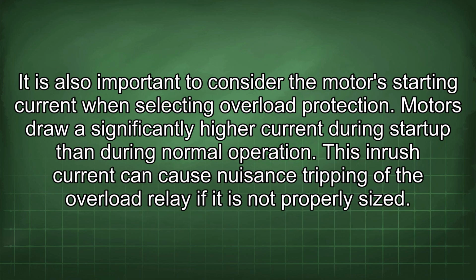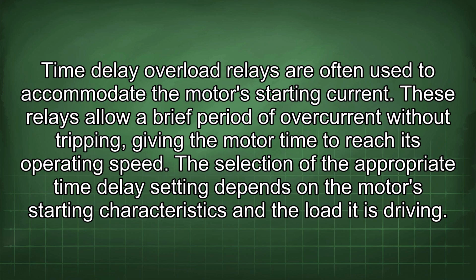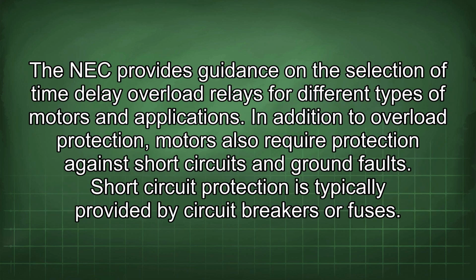It is also important to consider the motor's starting current when selecting overload protection. Motors draw a significantly higher current during startup than during normal operation. This inrush current can cause nuisance tripping of the overload relay if it is not properly sized. Time delay overload relays are often used to accommodate the motor's starting current. These relays allow a brief period of overcurrent without tripping, giving the motor time to reach its operating speed. The selection of the appropriate time delay setting depends on the motor's starting characteristics and the load it is driving. The NEC provides guidance on the selection of time delay overload relays for different types of motors and applications.